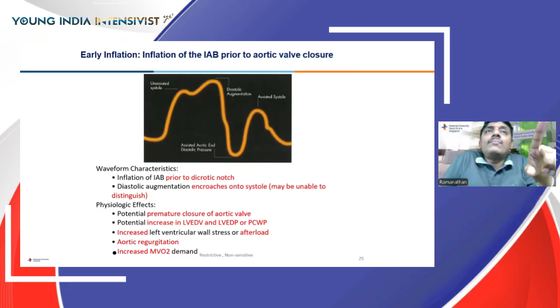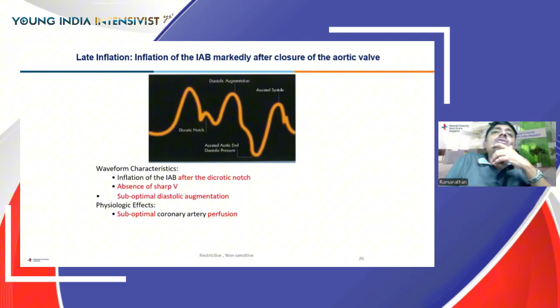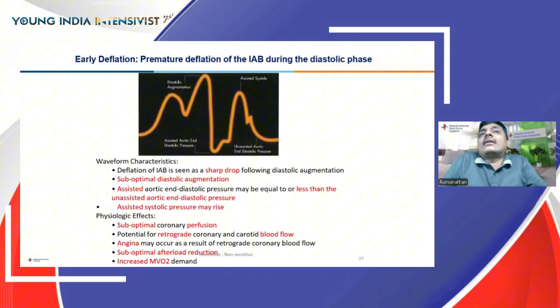You can also have a late inflation if you don't time it properly. Late inflation happens after the dicrotic notch, so there is suboptimal diastolic augmentation. The very purpose for which the balloon is used is not being fulfilled, and you need to be aware that it causes suboptimal coronary perfusion. You can have early deflation during the diastolic phase. Clearly, you will have not only suboptimal diastolic augmentation, but the assisted systolic pressure may also go up, leading to suboptimal coronary perfusion and increased myocardial oxygen demand.